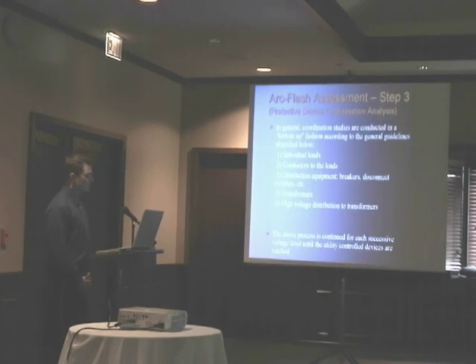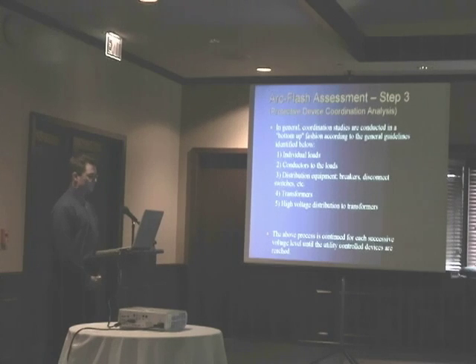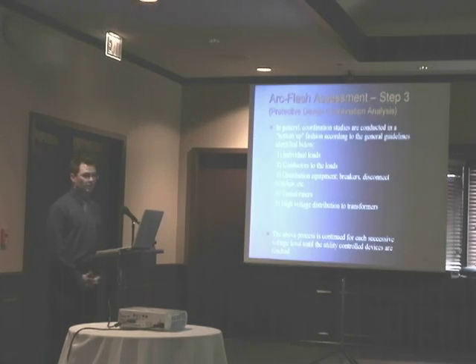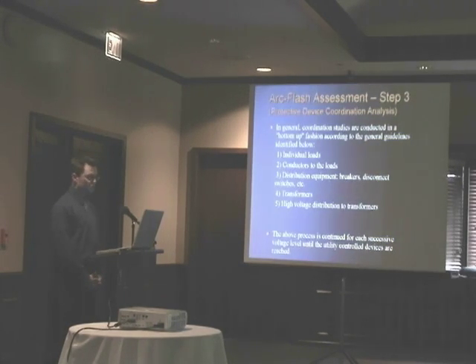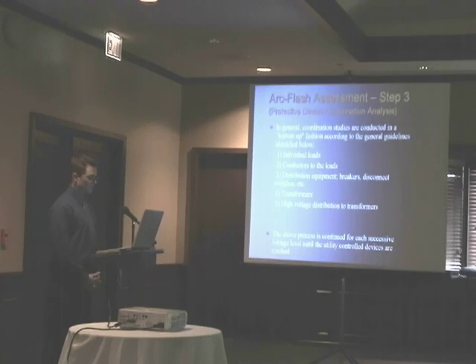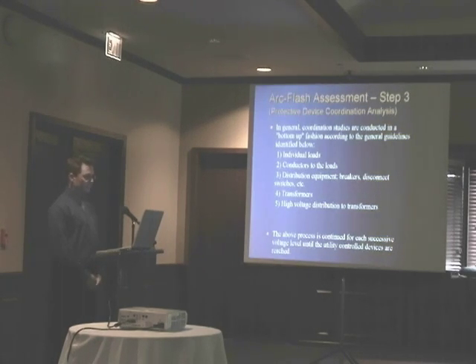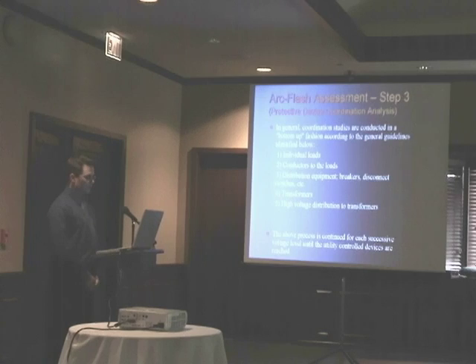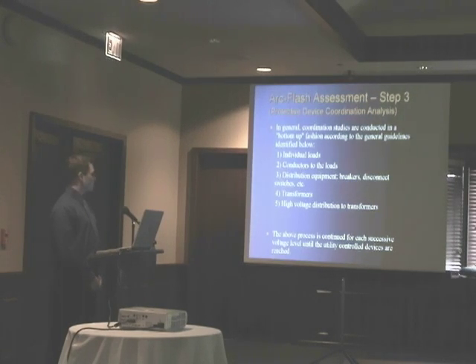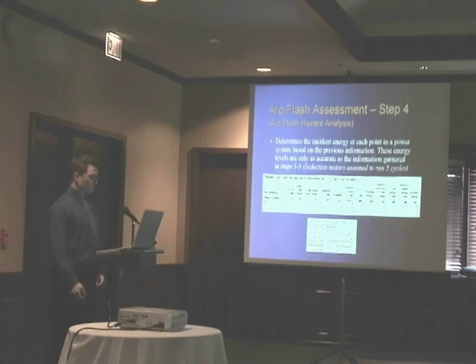In general, coordination studies are conducted in a bottom-up fashion, according to the general guidelines identified below. Like I said, we're going to start with individual loads, then conductors to loads, distribution equipment such as breakers and disconnect switches, and then transformers, and then your high voltage distribution to the transformers. Okay, the above process is continued for every voltage level until the utility control devices are reached.